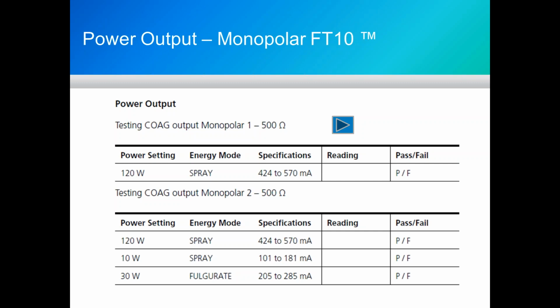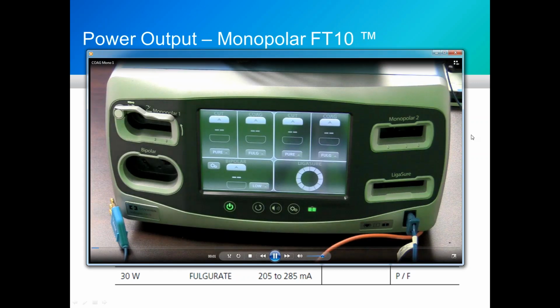And as such, we only need to do now one test on monopolar 1, and that is a CoAG test where our load resistance is going to be set to 500 ohms. So we're testing at maximum power, 120 watts. We're doing spray. And if we watch, we will see the video of that happening.